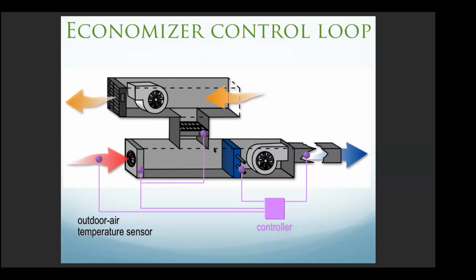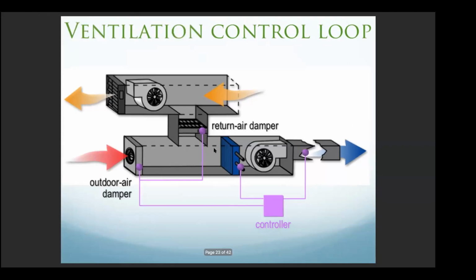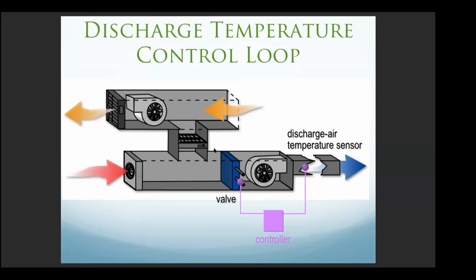So I would say refer back to these control loops and try to see how you can implement some of this in your existing projects. What you need to do is account for some of these sensors in your product spec of the equipment. So if you want the equipment to come with a discharge sensor, you better specify that in the spec, so that when the project goes out for tender and when it's awarded, the controls contractor is going to carry that sensor, or the manufacturer is going to supply that sensor.